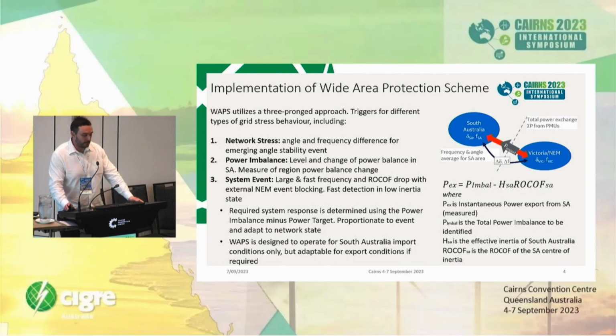It was a pilot project for a synchrophasor-based wide area protection scheme. And following the successful conclusion of the pilot project, the WAPS was developed, and it utilises a three-pronged approach. So there are triggers for different types of grid stress, including, as you can see, function blocks for network stress, so angle and frequency difference for an emerging angle stability event, and power imbalance. The power imbalance is used in two ways. It's used to trigger, but it's also used to determine the volume of response that's required, so a proportional response.